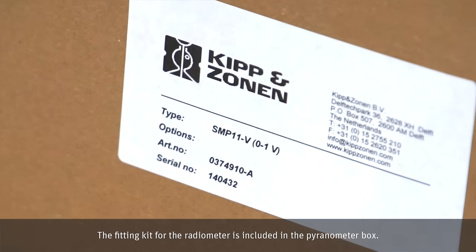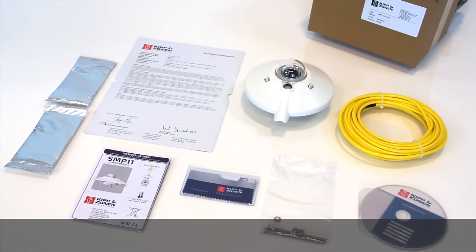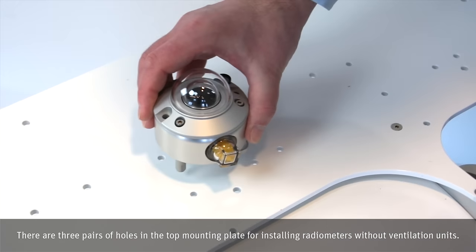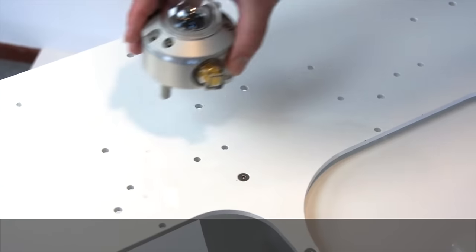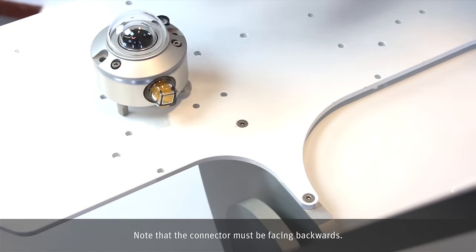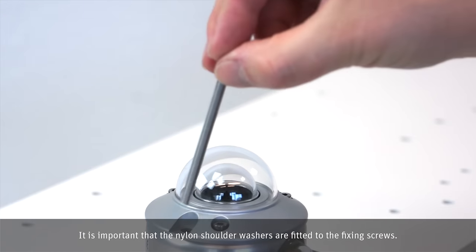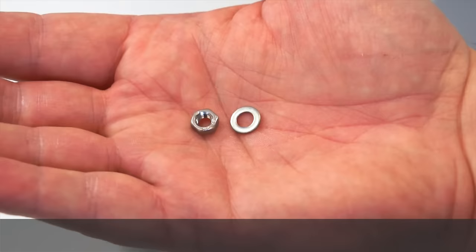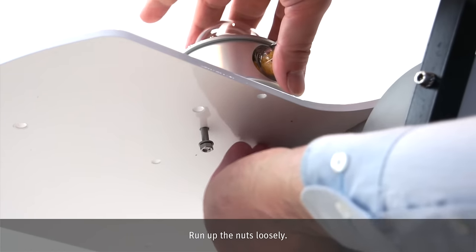The fitting kit for the radiometer is included in the pyranometer box. There are three pairs of holes in the top mounting plate for installing radiometers without ventilation units. Note that the connector must be facing backwards. It is important that the nylon shoulder washers are fitted to the fixing screws.